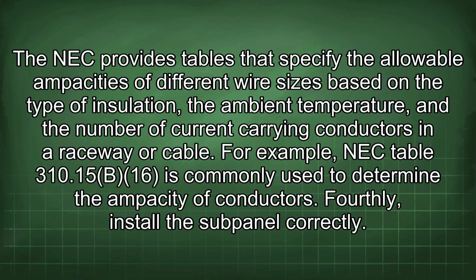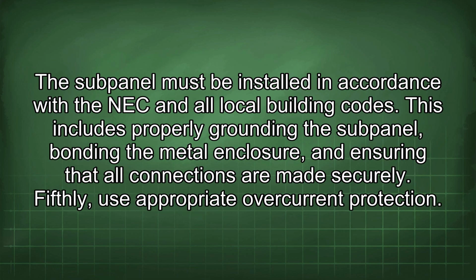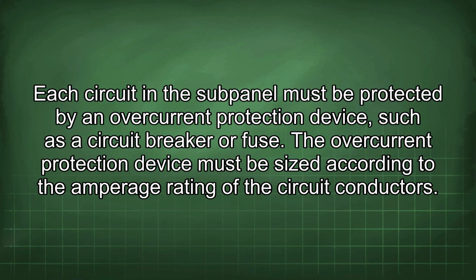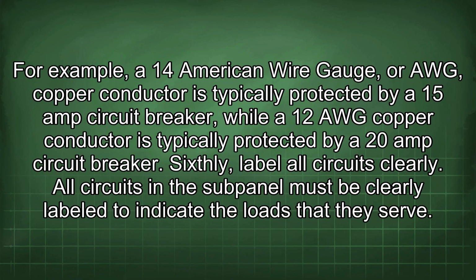Fourthly, install the subpanel correctly. The subpanel must be installed in accordance with the NEC and all local building codes. This includes properly grounding the subpanel, bonding the metal enclosure, and ensuring that all connections are made securely. Fifthly, use appropriate overcurrent protection. Each circuit in the subpanel must be protected by an overcurrent protection device, such as a circuit breaker or fuse. The overcurrent protection device must be sized according to the amperage rating of the circuit conductors. For example, a 14 American Wire Gauge or AWG copper conductor is typically protected by a 15 amp circuit breaker, while a 12 AWG copper conductor is typically protected by a 20 amp circuit breaker.